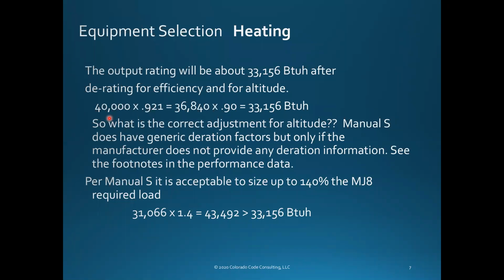So if I ever see a plan that comes in and it says, hey, I'm going to be more like 180% oversized, but the reason I did that was because I needed a bigger blower to get my air conditioner to work, as soon as I hear that, I say, oh, okay, let's move on with life. That is very unique to high altitude applications. Okay, we got that.